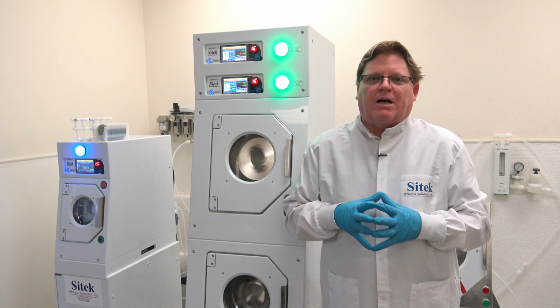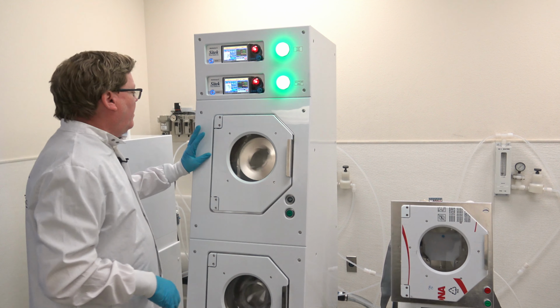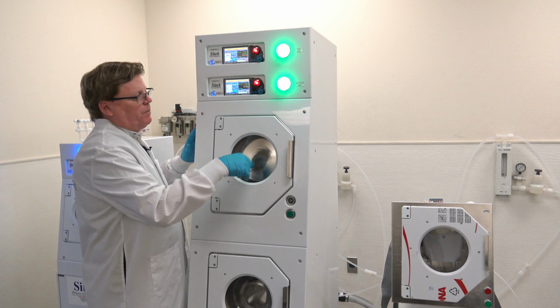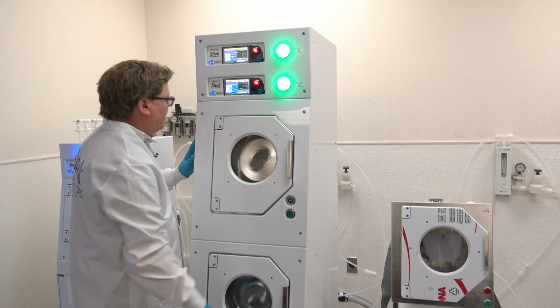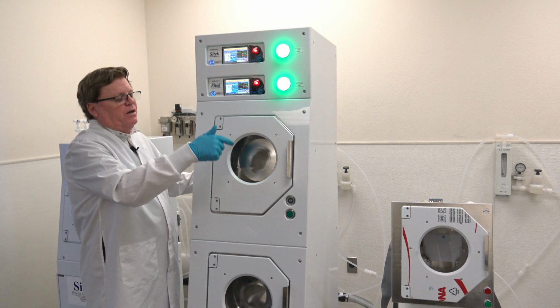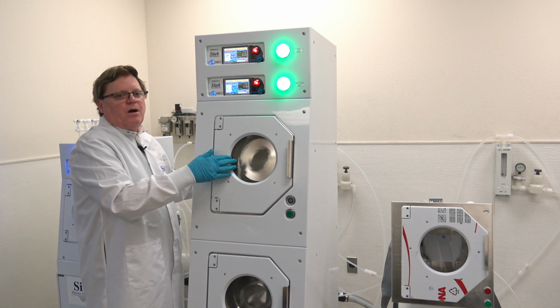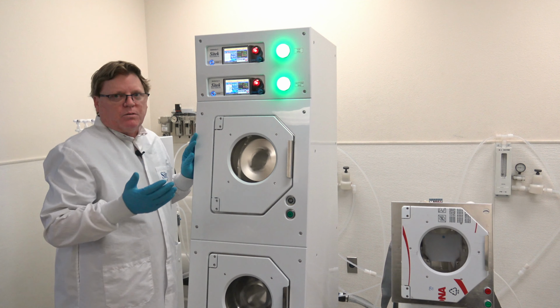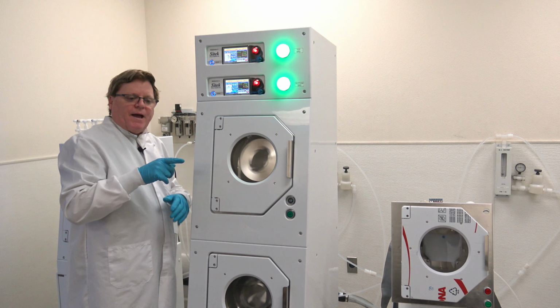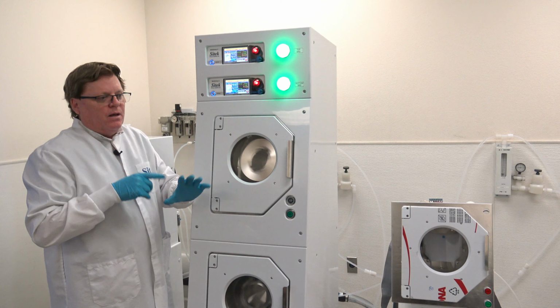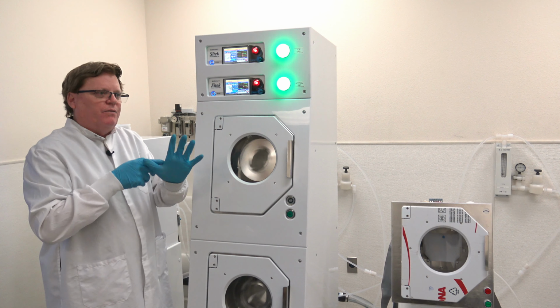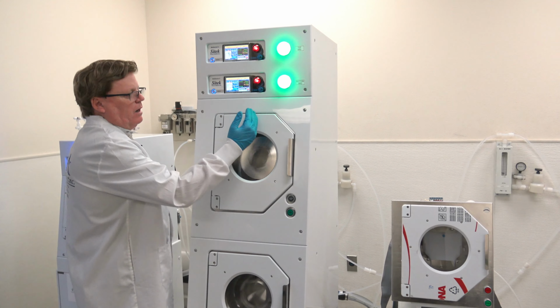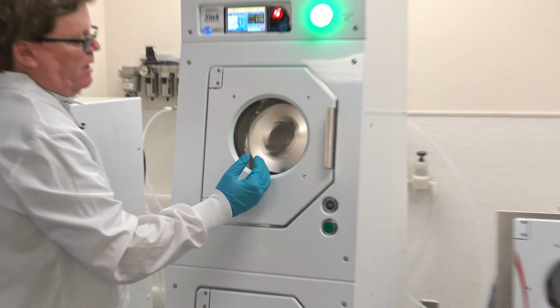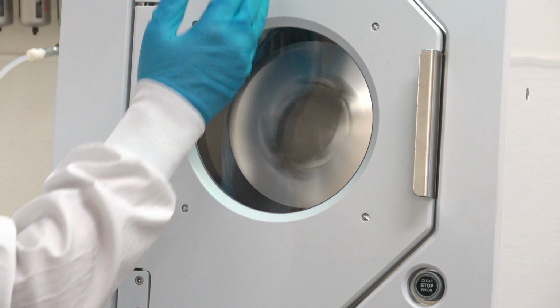We have about a minute left in this process. At the end, as we're spinning down, the doors are locked now and you can't open them. When we hit 70 RPM, the RSP, or rotor stop positioner, fires in the back. We call it firing, it extends out, goes against the cam assembly, finds what we call home position, and uprights the rotor to 12 o'clock. That's what we call home.